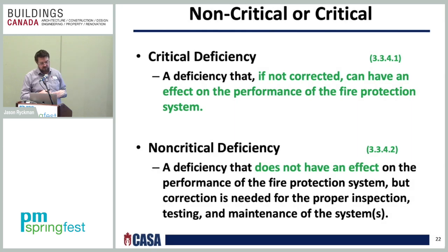So a critical deficiency is basically, if not corrected, it can have an effect on the performance of the water-based fire protection system. And a non-critical deficiency does not have an effect on the performance of the fire protection system, but correction is needed for proper inspection, testing, and maintenance of the system. So an example of a non-critical deficiency would be you're missing sprinkler heads in the head cabinet.